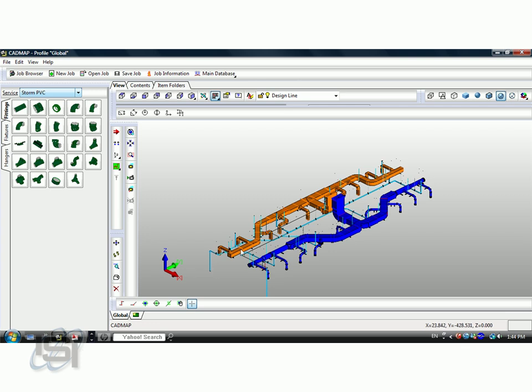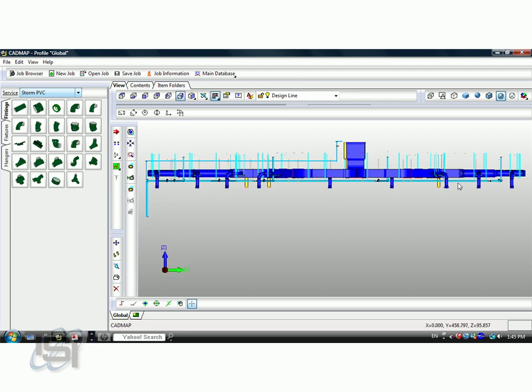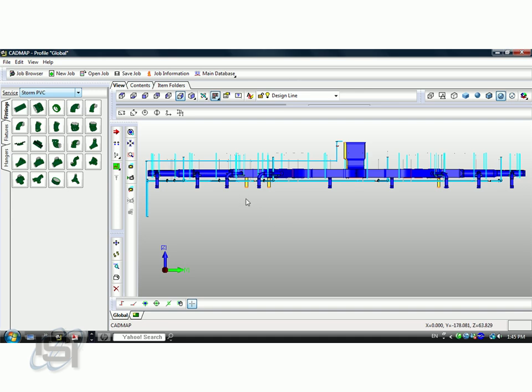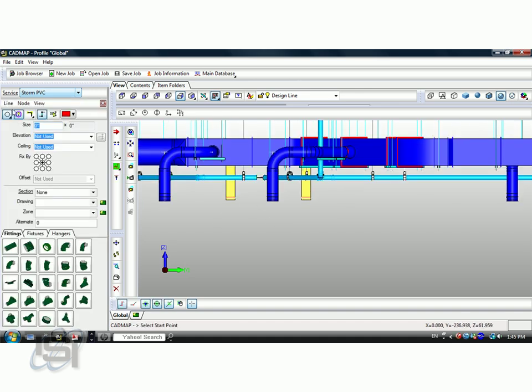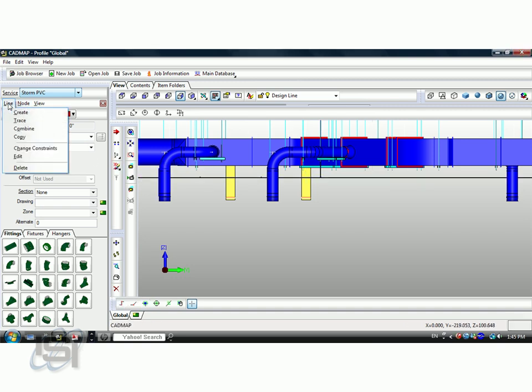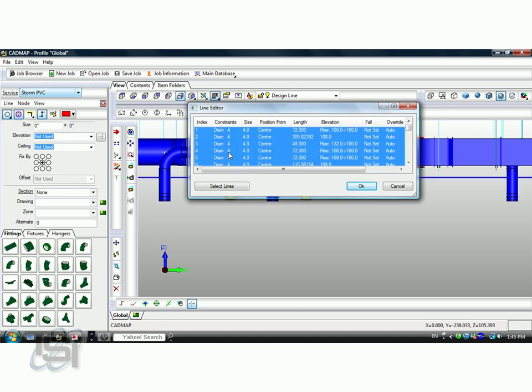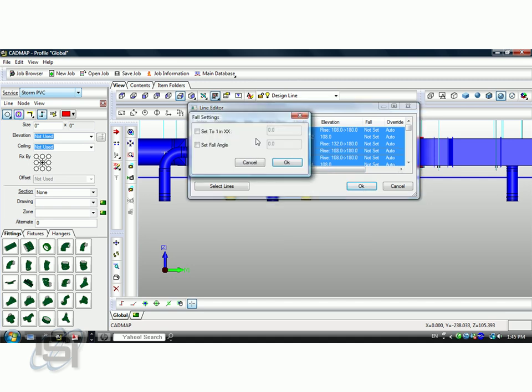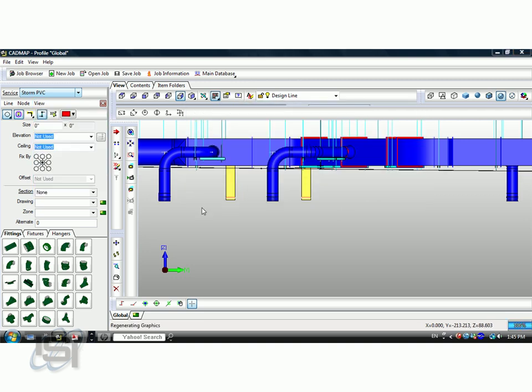What I'd really like to do is go ahead and define that to be a slope system. If I go ahead and put that in the side view here, you can see it's just flat. So I'll go ahead and modify that system. I'm making this DesignLine active and I'll just take off those piping materials. I'll go to Edit, use a Windows Selection Set to grab those components, and I'm going to right click and go to Fall. I'm going to go ahead and set that Fall here at 1 in 96 and you'll see that line slope out as I go ahead and autofill that.